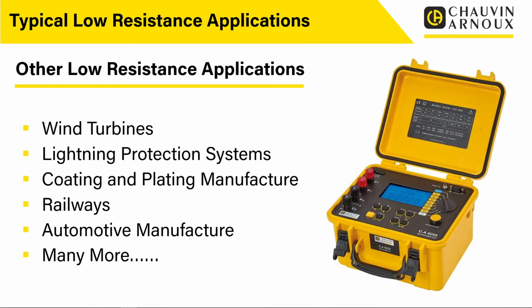Now, there are a few other applications that are just worth mentioning. Things like wind turbines, again generally for lightning protection, are all bonded together. Effectively the blades on the wind turbine are connected to the body and connected down to earth. So these things need checking and measuring, and generally it will be a low resistance ohmmeter that's used for that.